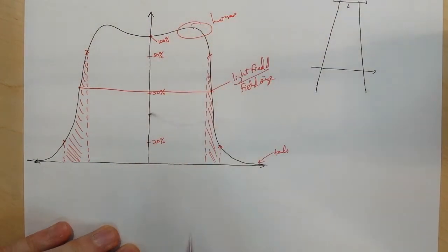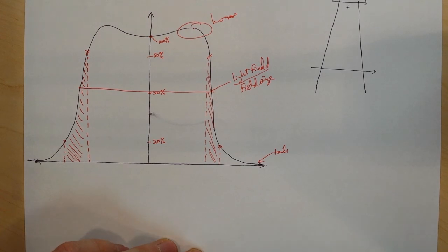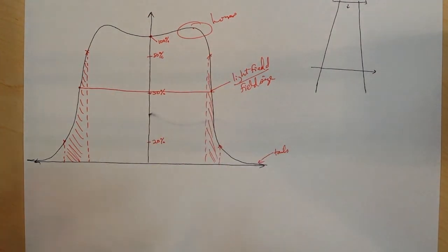These up here we call horns, and they vary in size depending on the energy that you use and the depth that you're at. And the horns are caused by the flattening filter of the beam. We can hopefully discuss that at a later time, why that's the case. But they will be there at shallow depths, and they will not be there at deeper depths. Most machines are designed to have their flatness and symmetry specified at a depth. Whether that's Dmax or 10, most of the time it's 10, since most treatments are at depth rather than Dmax, so they make it flat at 10 centimeters.